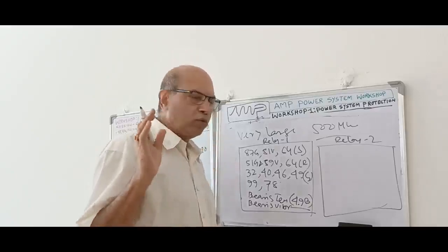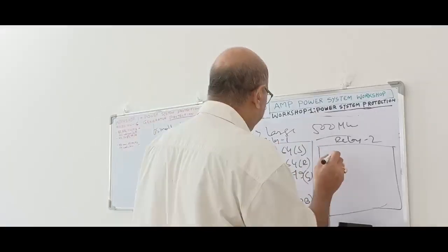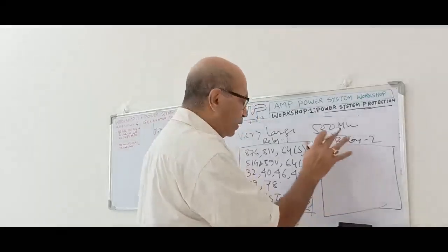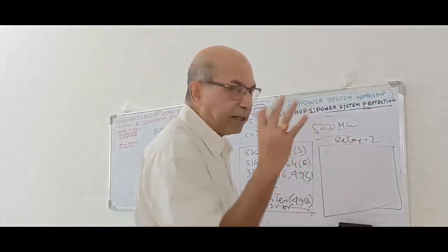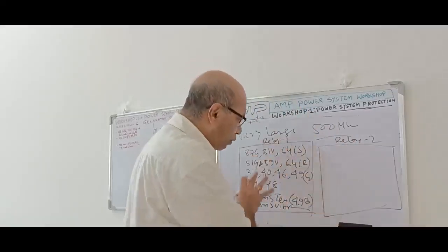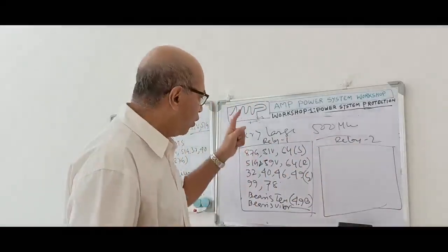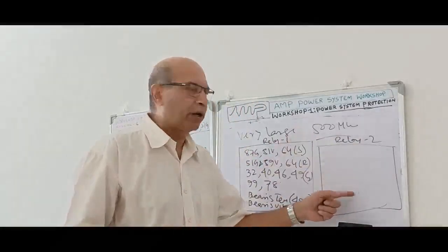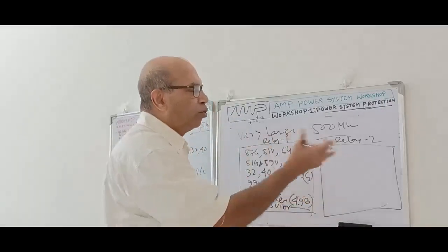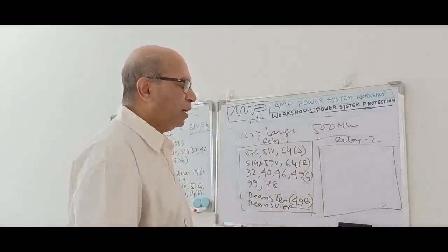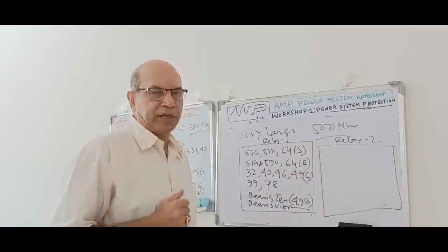Okay. These are the two ways of protection we can give it. This is the second set of relay with a separate set of CT and PT, including all the protection inbuilt over there. That will be the second duplicate protection. If one of the relays fails, then the second set of relay will work. So for the big size machine, it will be duplicated. That is the protection for the second set of very large size machines.